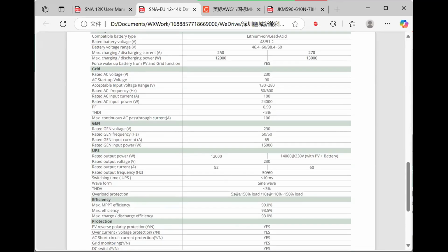The second question is, during the power interruption, can the inverter run a high starting current motor? I think it depends on the actual specifications and parameters of the motors. You can refer to the EPS and UPS output parameters of the inverters to check if they are suitable for the parameters of the motors.